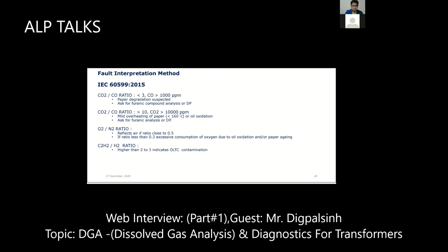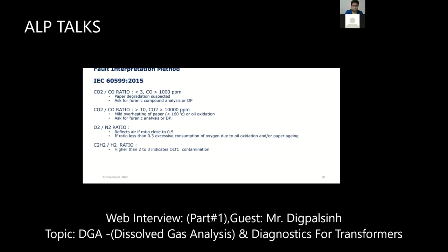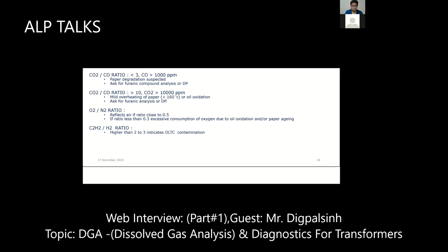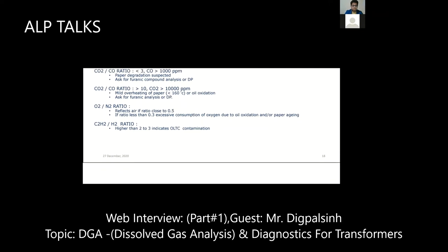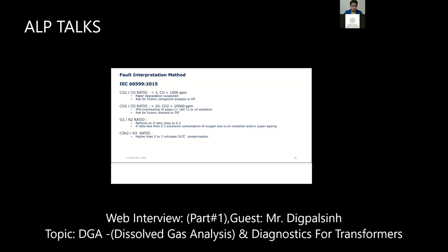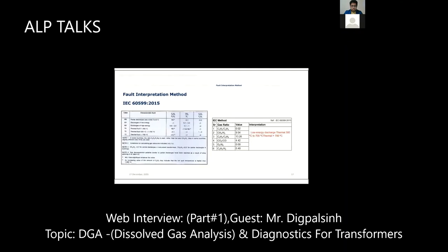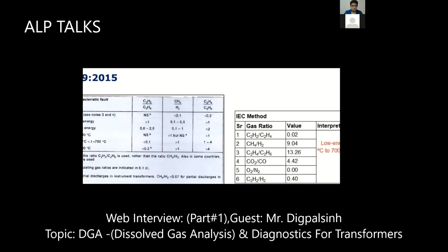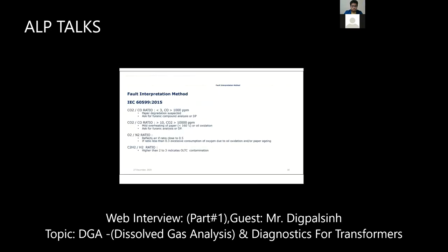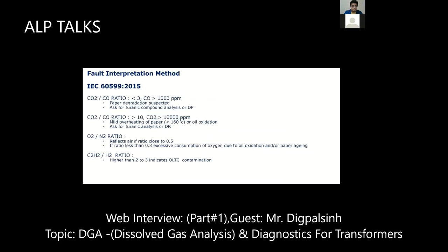Then the oxygen and nitrogen ratio. Then the last one is C2H2 upon H2. Higher than 2 to 3 indicates OLTC contamination. Here there is the CH4 and H2 ratio, and later on they have more categorized acetylene with hydrogen. As I have said, if the transformer tank oil is contaminated with OLTC oil and you find C2H2 in your transformer oil, you can say there is arcing inside the transformer.